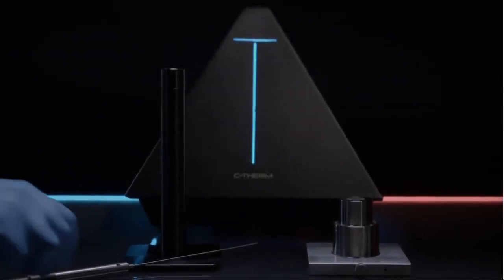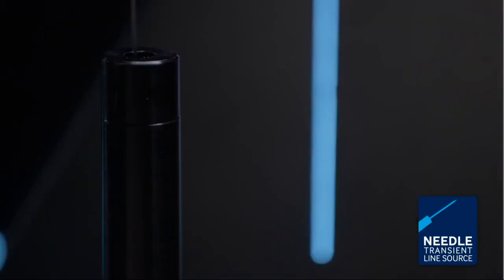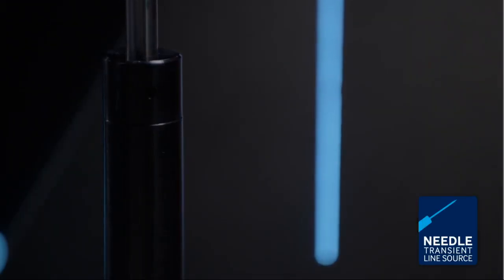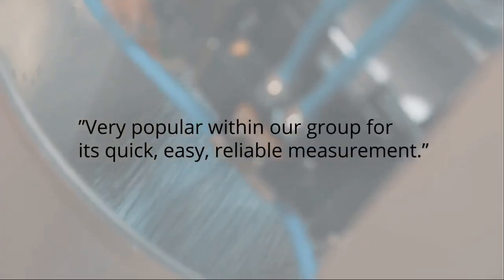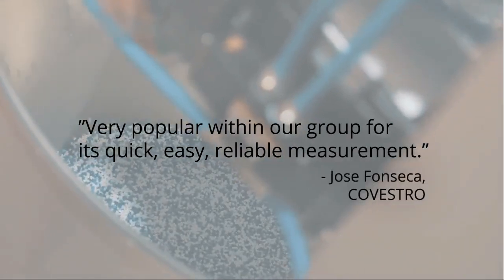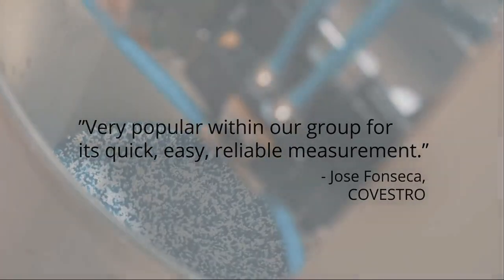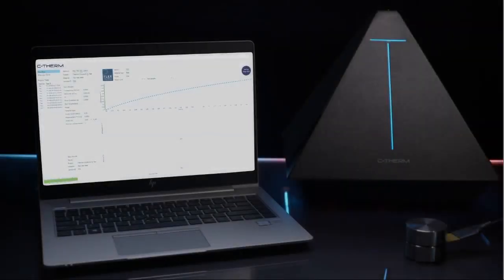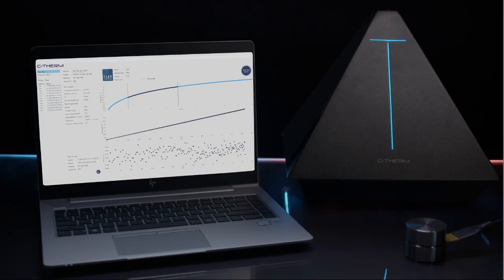Sheathed in stainless steel, the TLS, Transient Line Source Needle method, offers maximum robustness in thermal conductivity testing. TLS is best suited for granular materials, polymer melts, soils, slurries, and gels. C-Therm software provides full data acquisition and analysis in one user interface, allowing full control of all 3 methods. Intuitive, logical, easy.